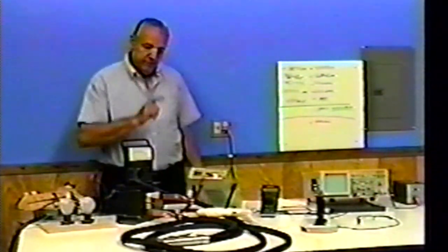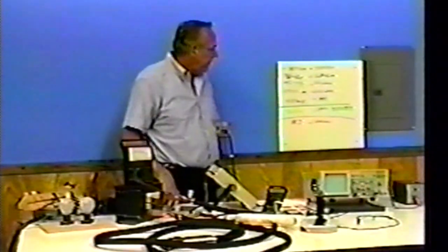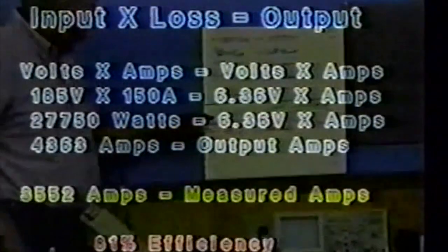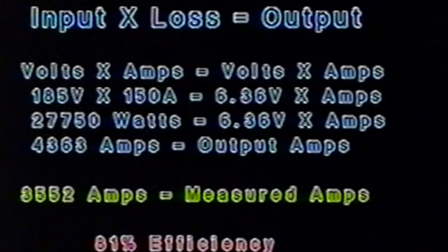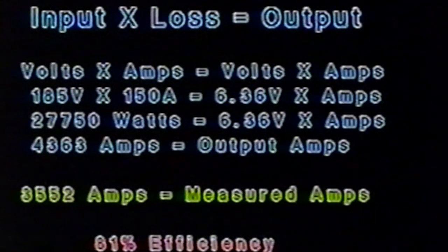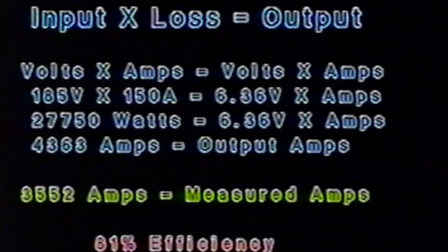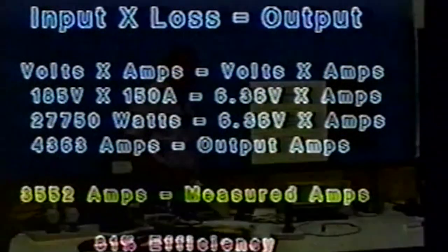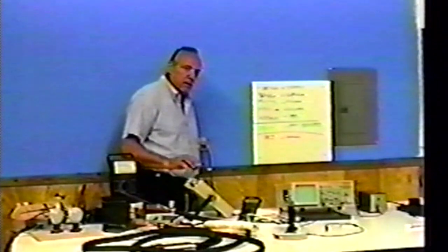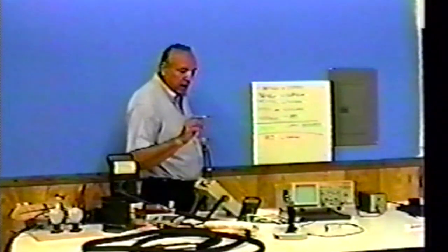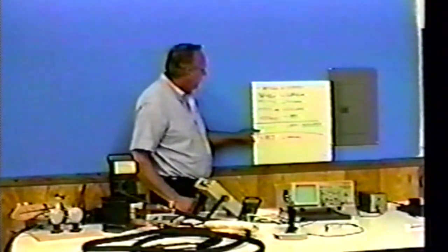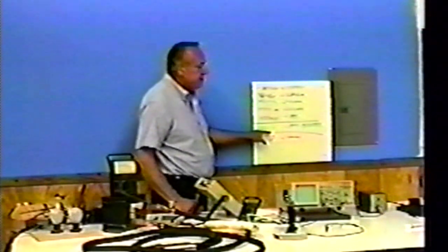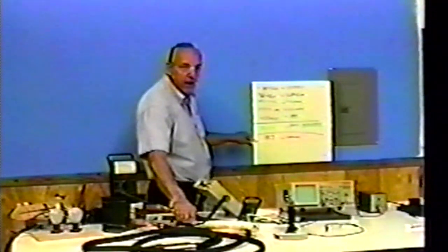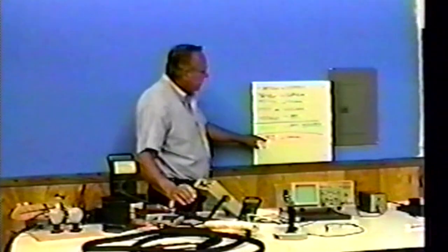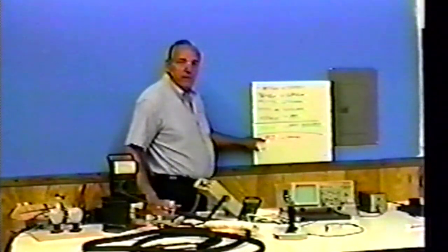So I'll be right back in just a minute. I'm back now. I've measured the amount of amperage this has, and according to this coil and this Fluke digital meter with 1 or 2% accuracy, I've determined we have 3,552 amperes of measured current coming out of the transformer. That gives us an efficiency of 81%.